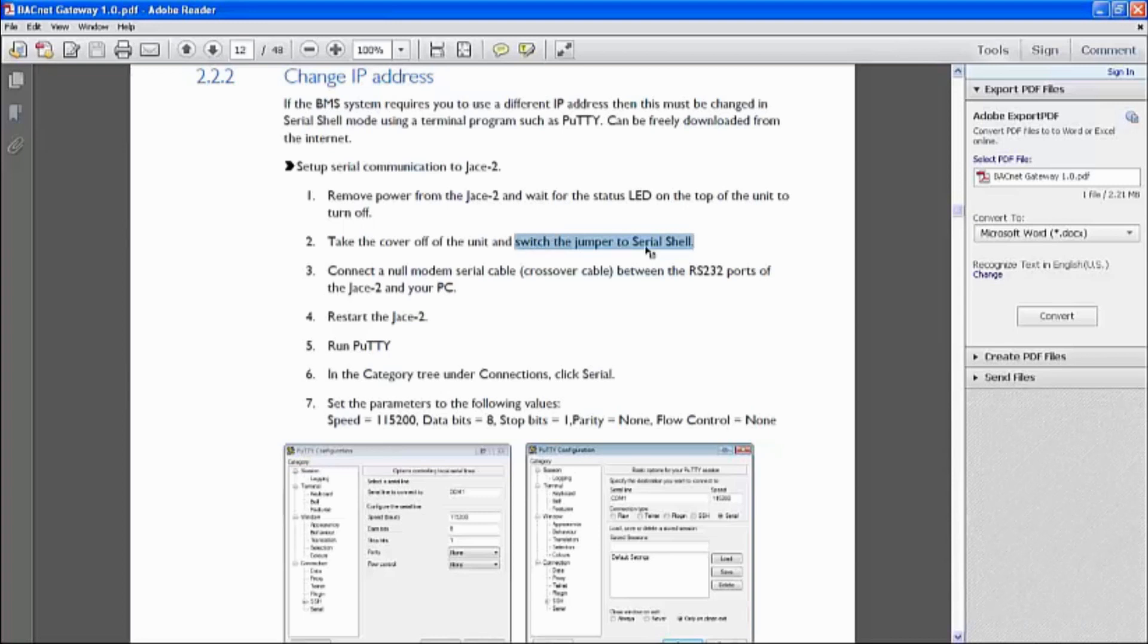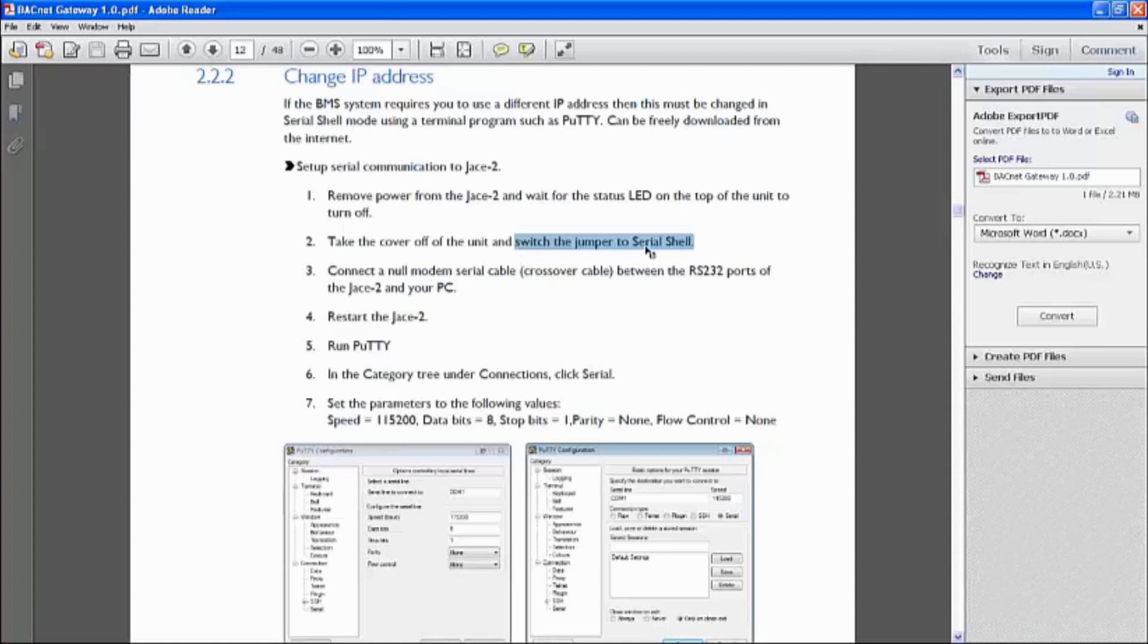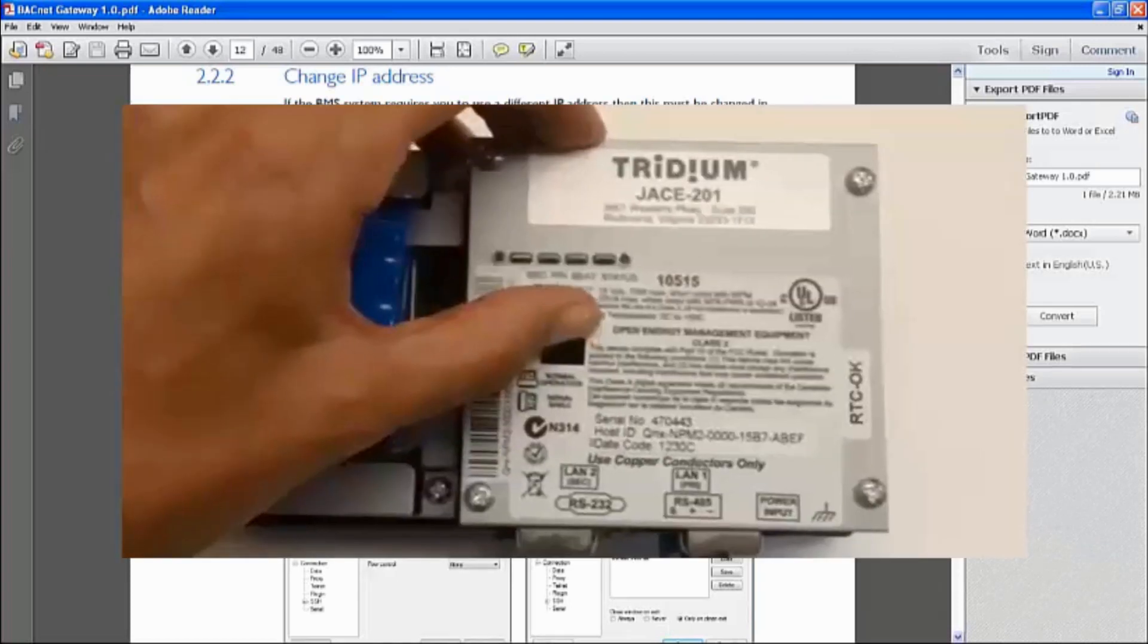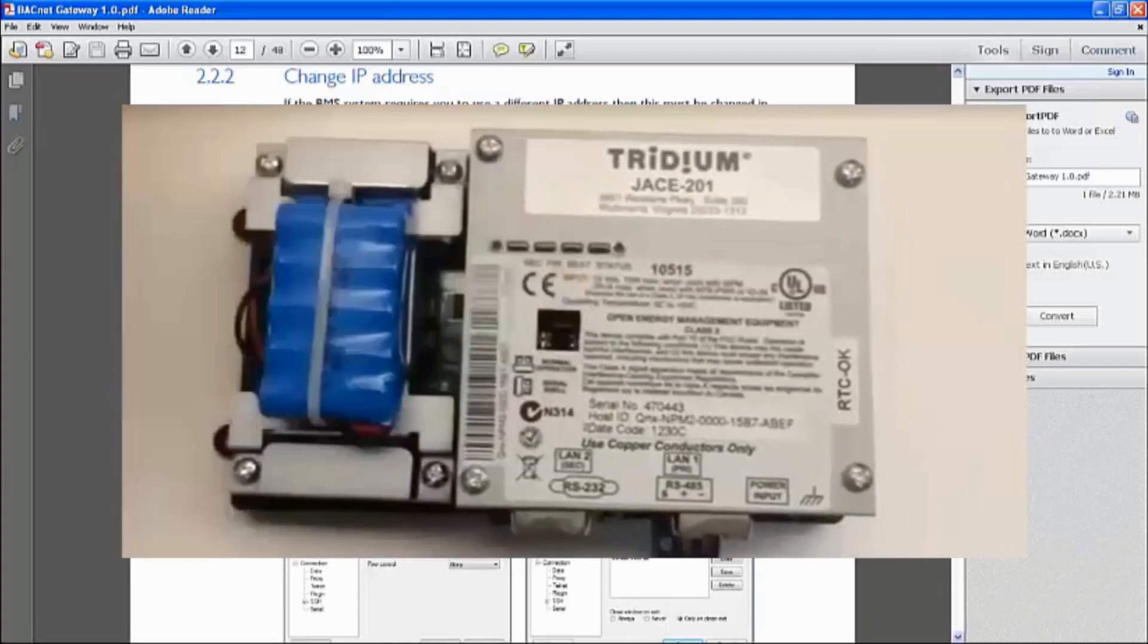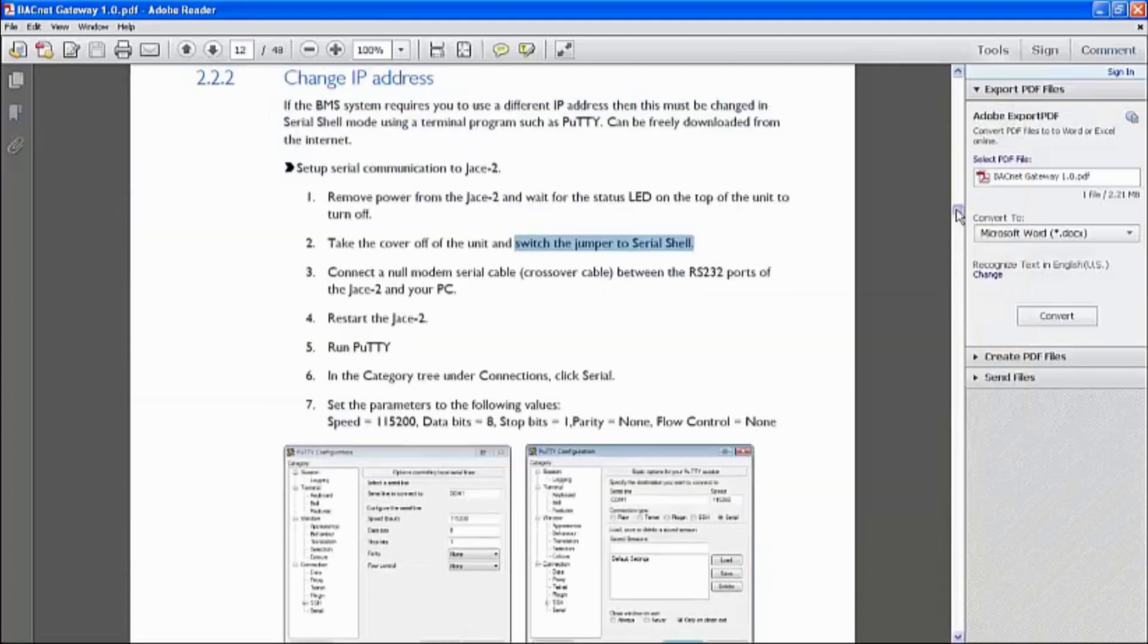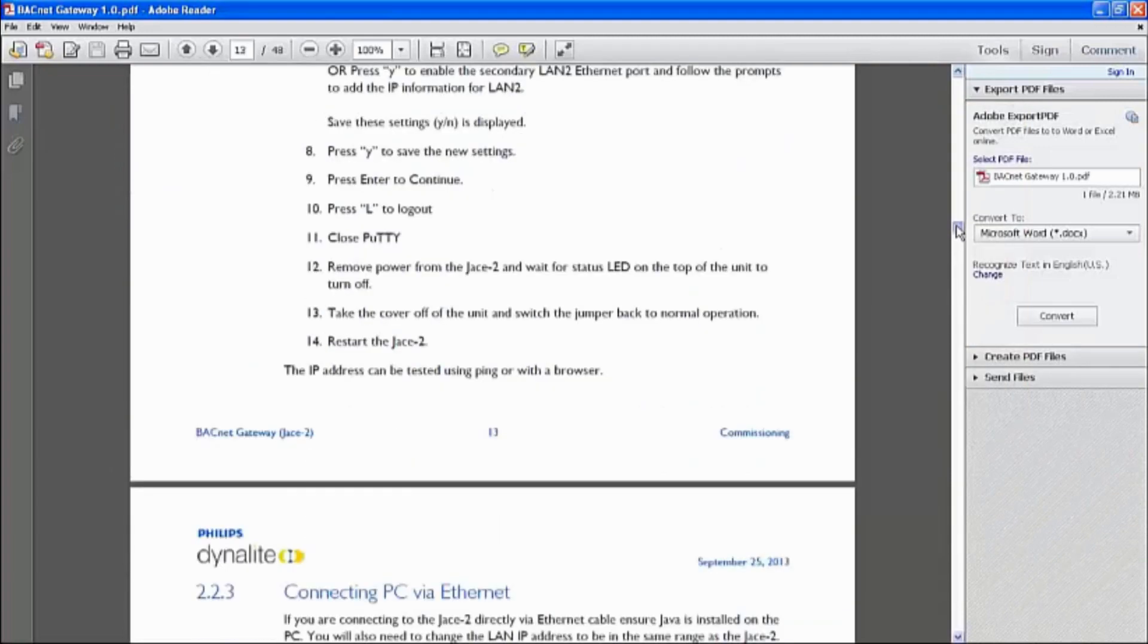But take note of this. This is very important. Take off the cover. Power down the unit. There's a jumper wire. By default, it's in a normal operation. But if we need to change the IP address or to update the drivers, we need to change it into the serial shell position, which will be vertical. And by default, it's horizontal on normal operation.